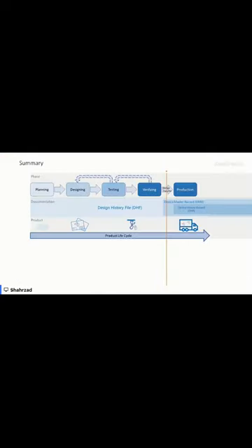So we'll be moving on to, yes, so these are just a few examples, just a small list of forms and files in a DHF, design history file, that is developed by the new product development engineering team in a company, right? So things like testing plan, design requirement trace matrix, design input, and design and risk management plan. These are all examples.